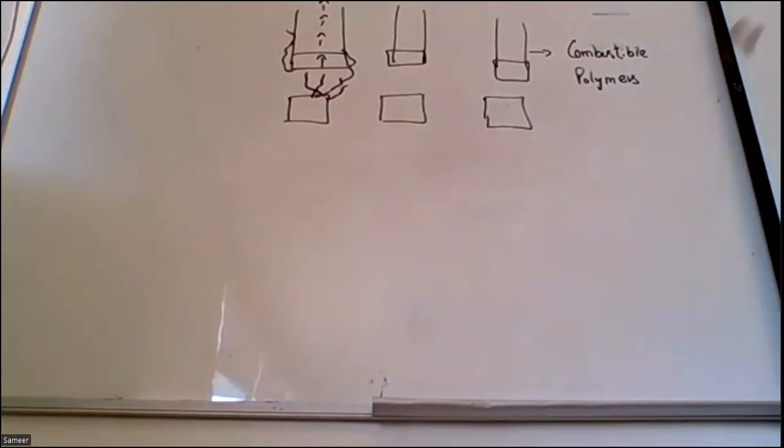These sacrificial ducts are usually vertical, or they could be horizontal both. They are usually composed of combustible polymers. They are sacrificial ducts that we tend to install, just one of the other techniques in the theory of extinguishment, where we can direct the flame towards a more combustible material that is available nearby.